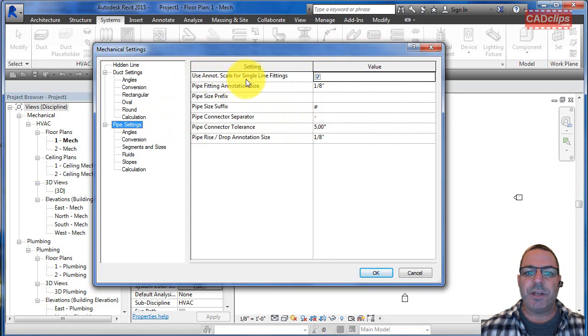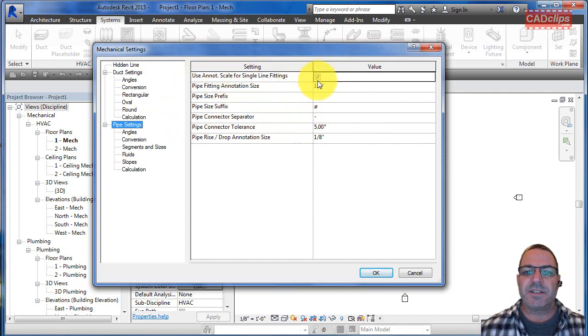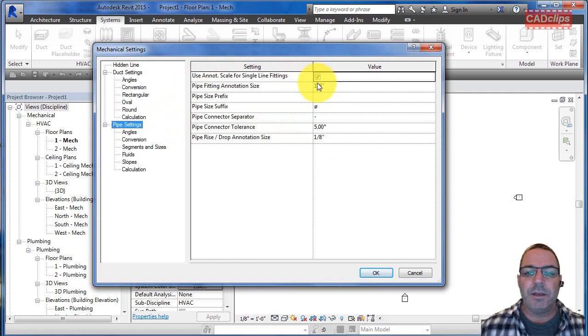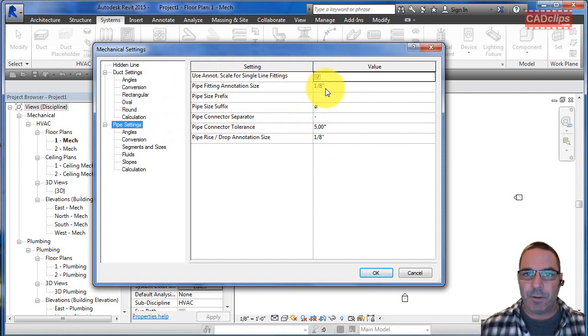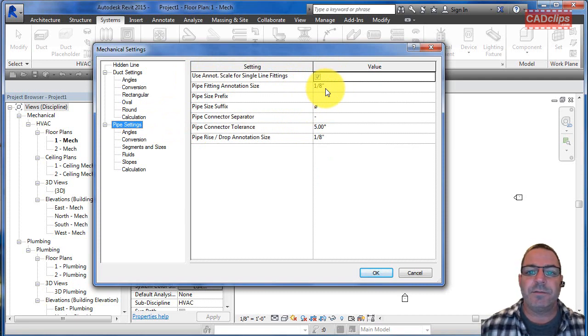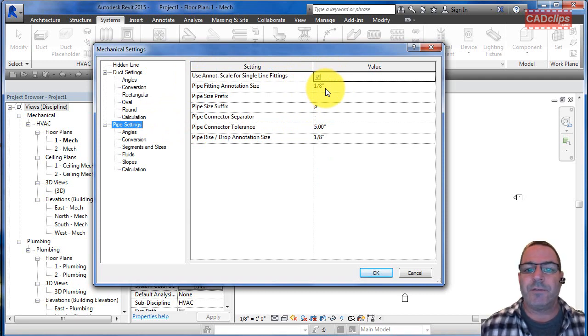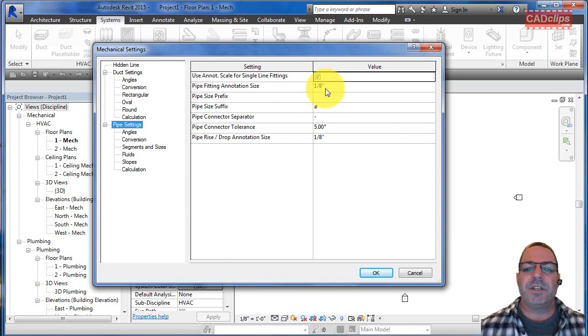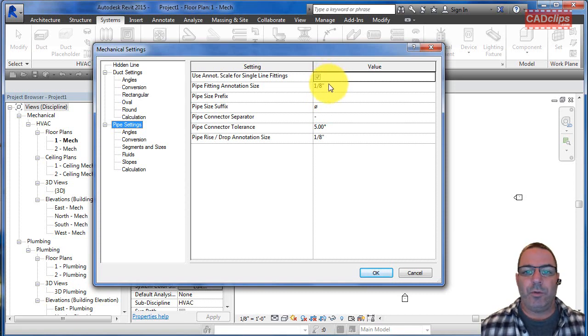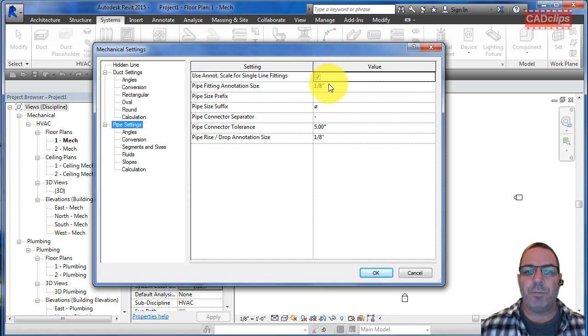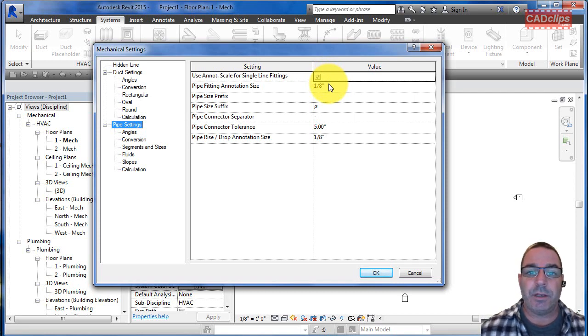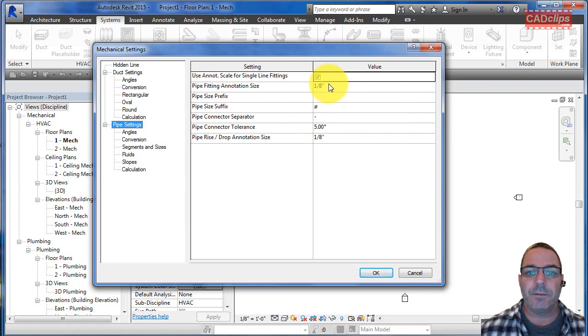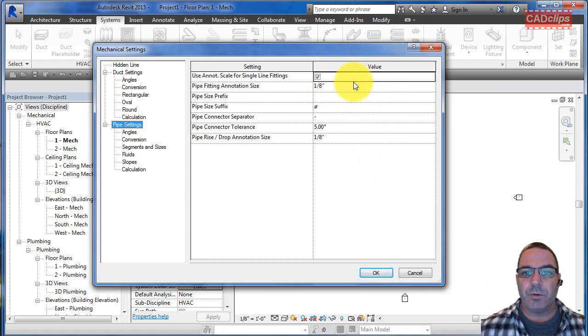These two settings are set inside of here with both piping and duct settings. Use annotation scale - if this is turned on, the symbols will globally adhere to this size. Then it defers to the family itself. If you don't like the size at all, then you have to edit the family, but this will control them globally. Take note of these settings inside of here.